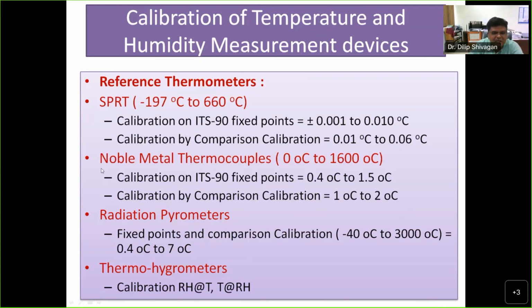Then noble metal thermocouples: always use a noble metal thermocouple if you are using a thermocouple as a reference, because base metal thermocouples are not very reproducible. They are cheap, their sensitivity is larger, so you can use a rather poor indicator. Suppose a copper-constantan or K type will have 34 microvolts per degree at 1200 degrees Celsius, while type S has only 12 microvolts change. But the 12 microvolt device is quite reproducible because it is a noble metal thermocouple. It has little or almost no contamination effects. But base metal always gets oxidation problems and other alloying problems. So there, if you calibrate at ITS-90 fixed points, then the uncertainty will be 0.4 to 1.5 degrees.